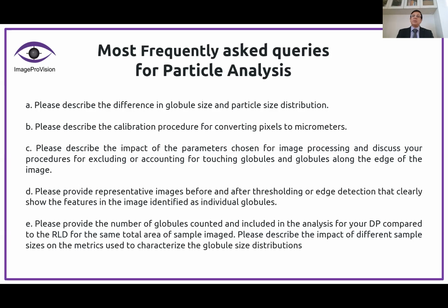Please describe the calibration process of converting pixels to micrometers. Now, since we are in this process, we are working on the images of the particles. So converting those images, that is in terms of pixels, into microns.